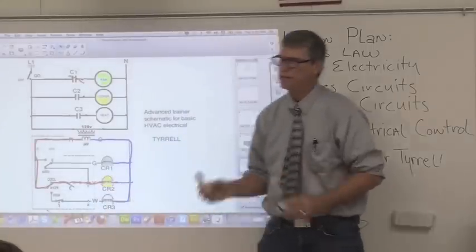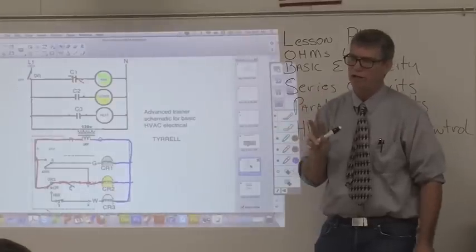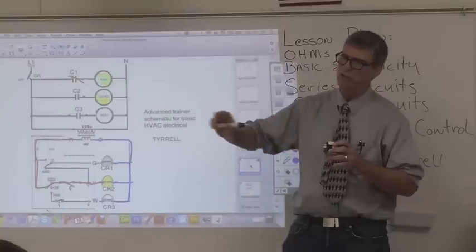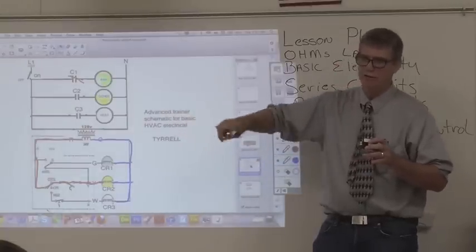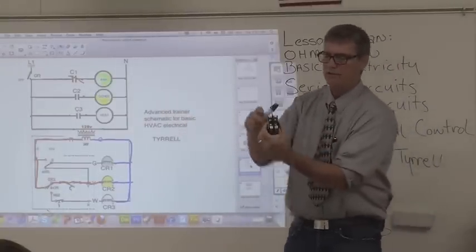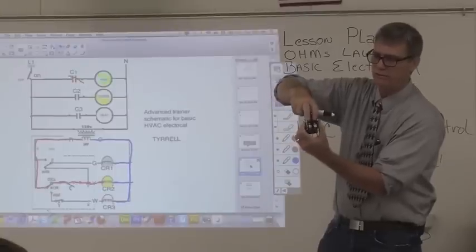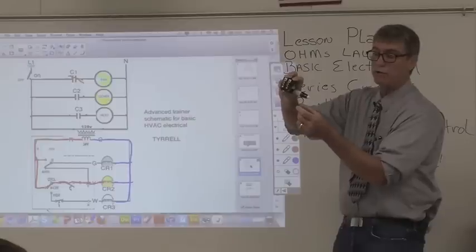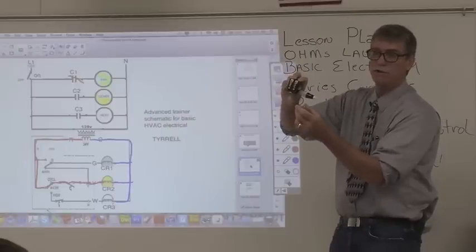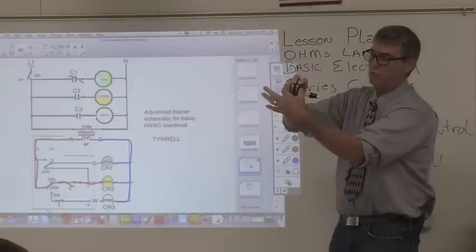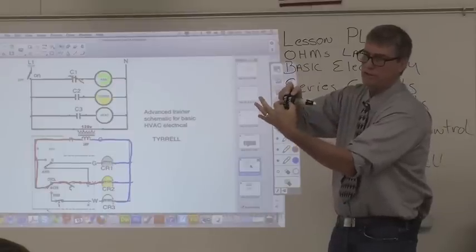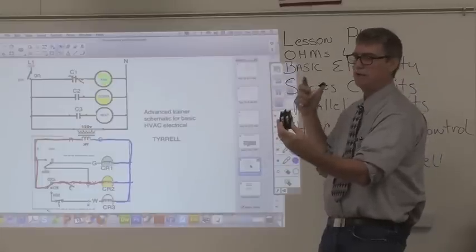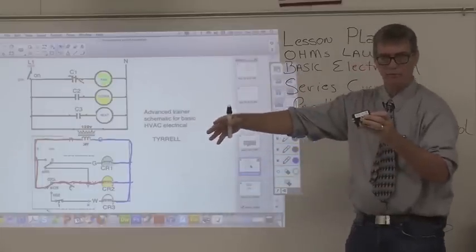There's a terminal inside the thermostat that has Y on it. When the thermostat wants cooling to start, it is going to send that 24 volt signal all the way outside on a low voltage wire and pull that contactor in. A typical compressor or condenser will have 208 to 220 volts on it. When this closes, it's going to take that L1 and L2 signal and power up the compressor and the condenser fan motor.